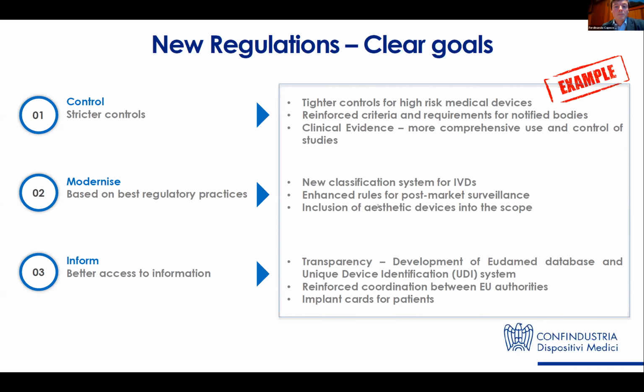Last, the third goal of the regulation was to implement transparency measures, especially with the development of the EudaMed database - a unique European database where notified bodies, economic operators, and manufacturers will have to upload all relevant documents regarding the device. We also have implementation of a new barcode, the unique device identification system, coordination between EU authorities, and other specific measures for specific devices.